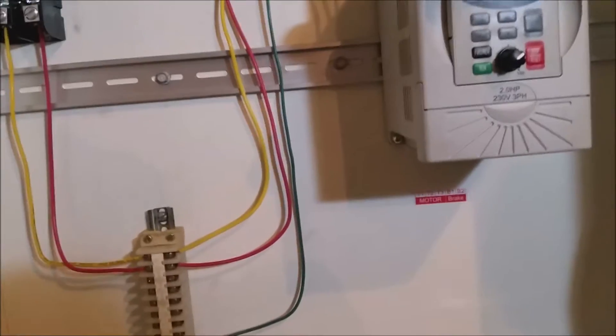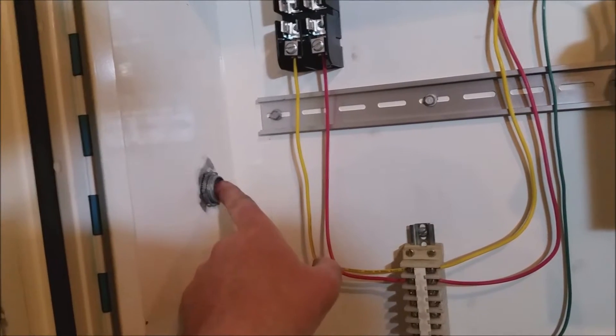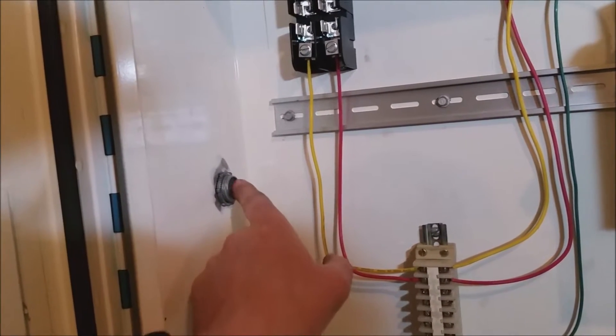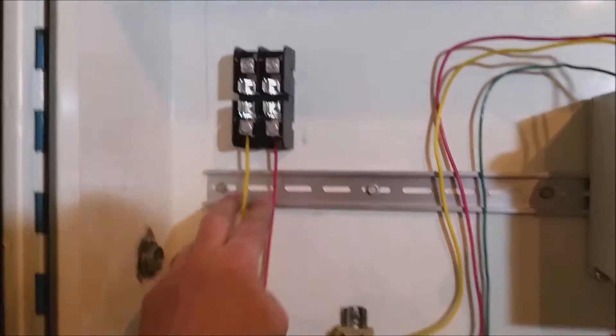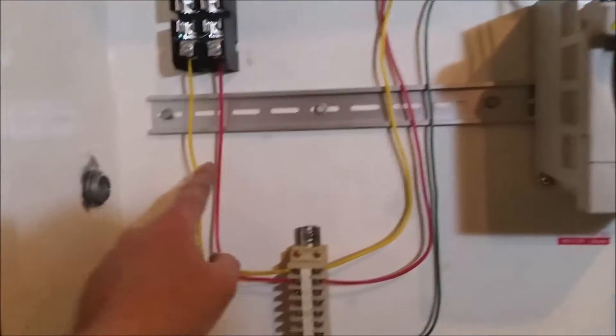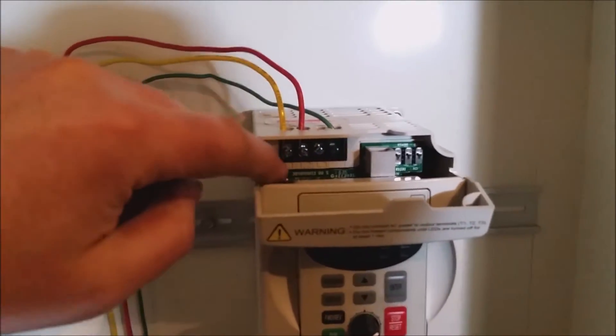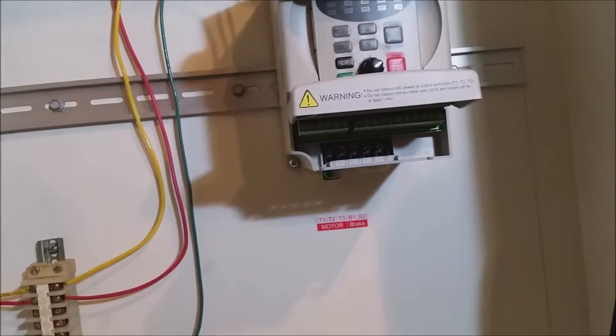What I've got so far is my 220 single phase power coming in here, going up to here, and then following down around. You can see the yellow and red wires following down to these first two leads on the top, which are L1 and L2. I've got a ground here, and then we'll start hooking up the three phase motor from down here.